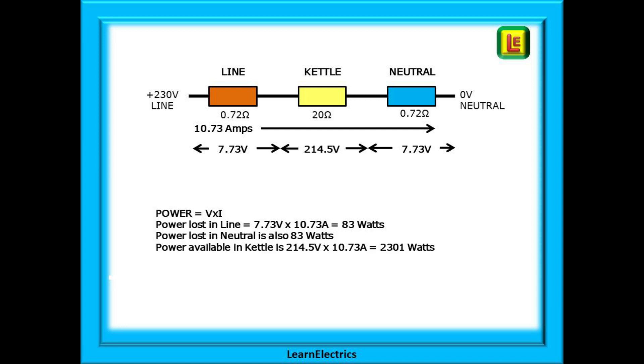Calculating power in each part: the line conductor has 7.73 volts times 10.73 amps = 83 watts; the neutral also loses 83 watts — meaning 166 watts of energy is being lost into the cables in the wall every time the kettle is switched on. This is lost energy the customer is paying for. The kettle receives 214.5 volts times 10.73 amps = just 2,301 watts. Our 2.7-kilowatt kettle is now functioning as only a 2.3-kilowatt kettle — all because of a long, thin cable installed without proper calculation.